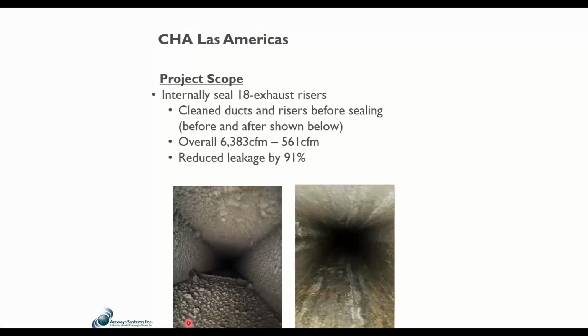It is common to clean the ducts before you seal them. You don't have to. You can have your dirty ducts sealed, but it's just kind of illogical. The dirt's getting in there through the leaks. You're finally going to seal them. Why not just get rid of all the crap and then seal it? So most people will clean the ducts and then seal them, but you don't technically have to do that. You can encapsulate the grossness in there forever if you want. So clean and seal is a common application strategy that many will do, but you don't have to do it that way.